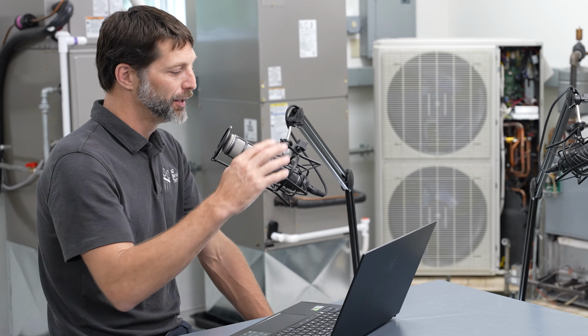Well, the problem is, you pull it down to 0, it's going to rise because a lot of that refrigerant is still trapped in the oil in the system. So just because you pulled it down to 0 PSI, that doesn't matter. You need to then turn the system off, monitor pressure for, say, 5 minutes, see if that pressure rises. If it does, you're going to have to recover that refrigerant again. And that's really going to be for a safety issue.